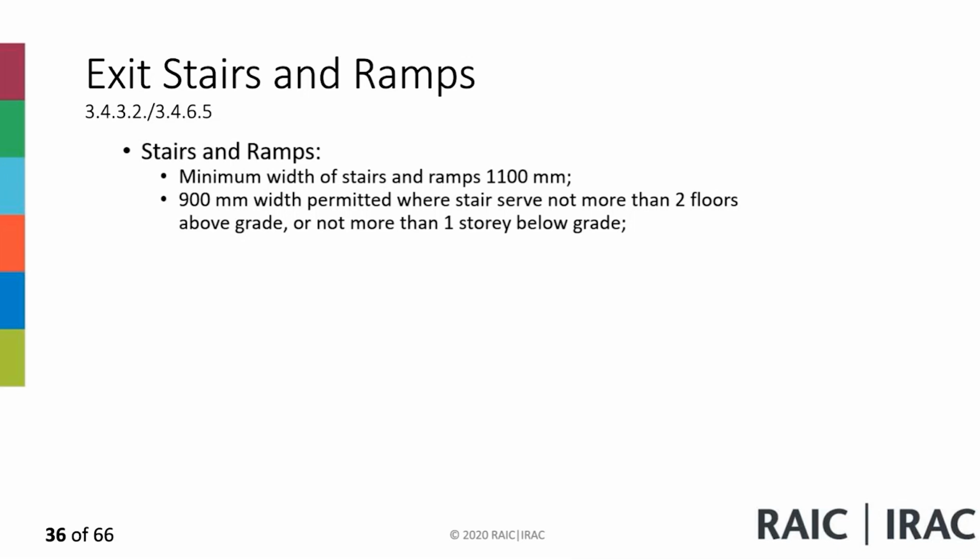So unless they meet the exemptions of 3.3.1.14(2), all egress stairs and all stairs and ramps within the floor area that are not designated exit stairs need to be designed based on the specific provisions of 3.4.3.2(8) and Articles 3.4.3.4 and 3.4.6.1 to 3.4.6.9. They don't need to meet all the provisions required for exit stairs, but only the specific provisions listed under 3.3.1.14.